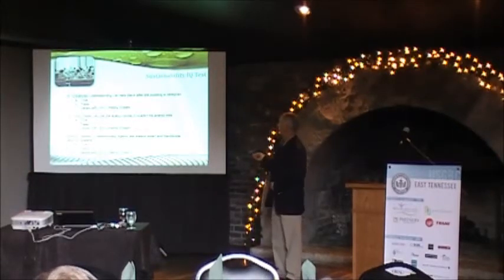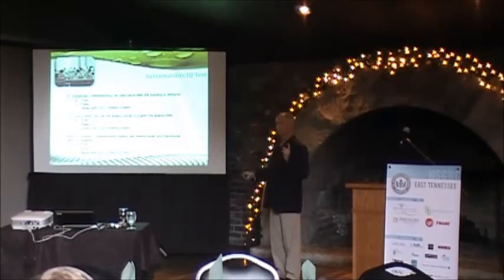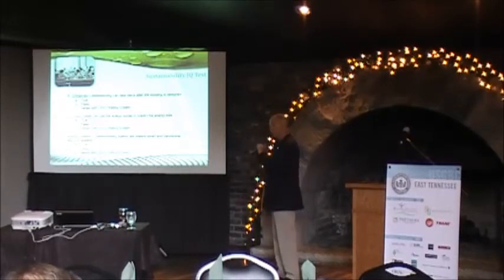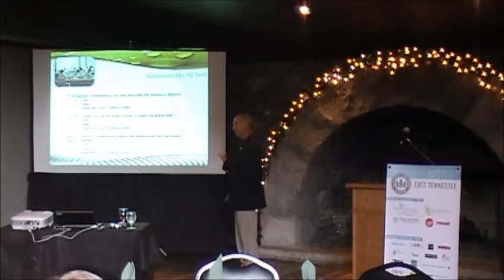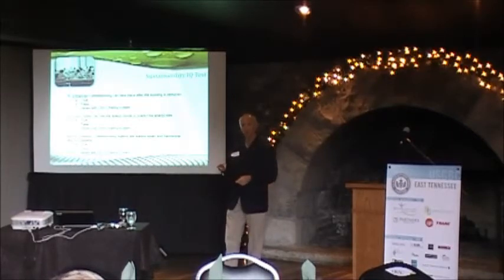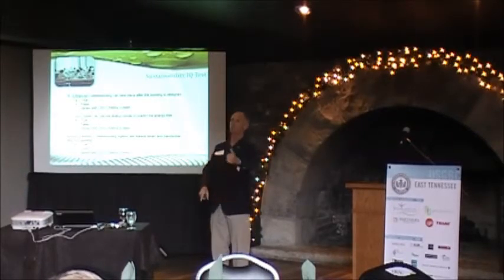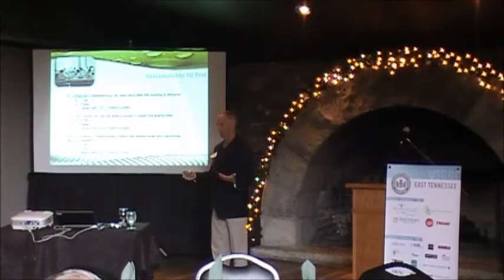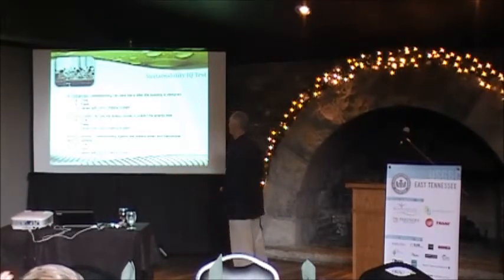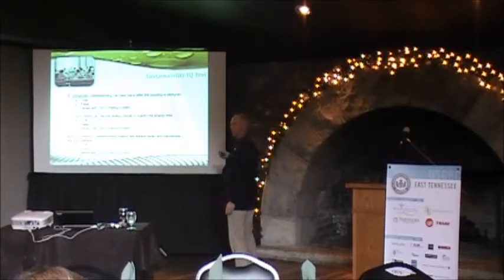Enhanced commissioning can take place after the building is designed - true, false, or varies? Enhanced commissioning includes design phase reviews, but it can take place after design. We found this out on a project: if the owner agrees that when you do a design review retrospectively and find something, they'll fix it. And of course, when you do the design review, you try to find anything really bad. But yes, it can be done - that's kind of a quirky thing.